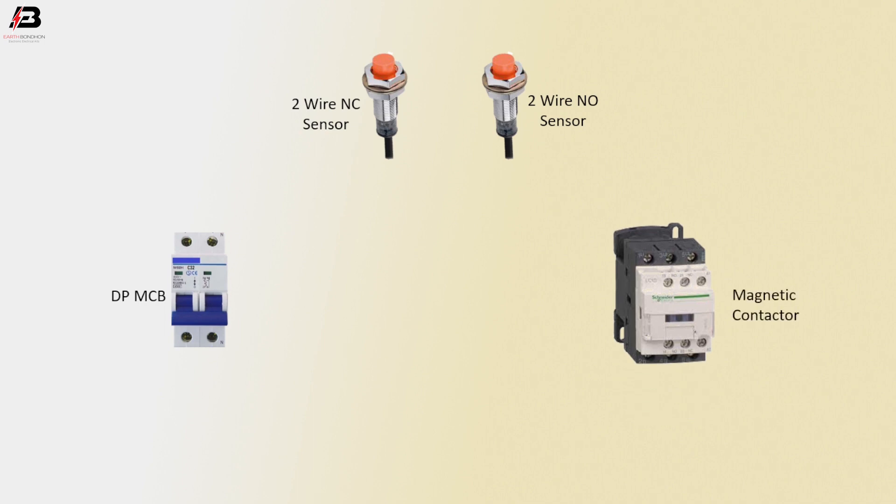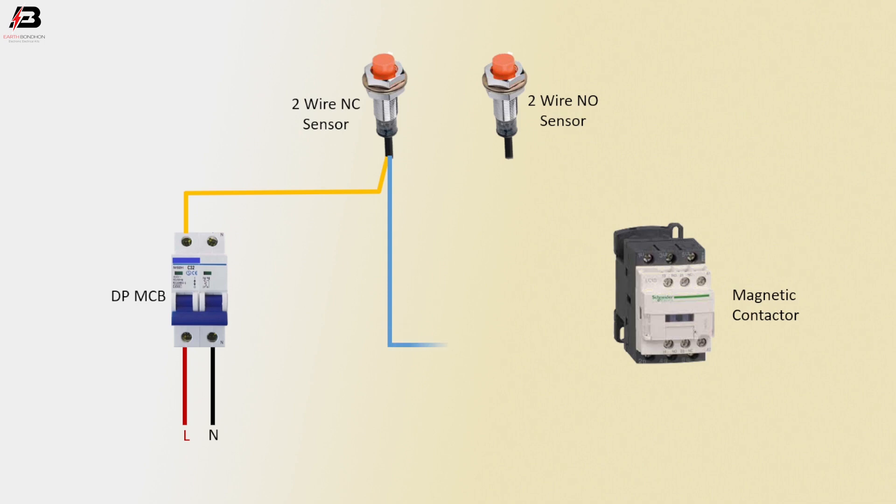Let's start. Double pole MCB, 2 wire NC sensor, 2 wire NO sensor, magnetic contactor — phase connection. DP MCB neutral connection to MCB neutral point. Face connection outgoing from DP MCB to 2 wire NC sensor. Face connection outgoing from 2 wire NC sensor to magnetic contactor NO point. Face connection outgoing from magnetic contactor NO point to 2 wire NO sensor. Coil connection with NO shot from 2 wire NO sensor. Neutral connection from DP MCB to magnetic contactor coil connection.